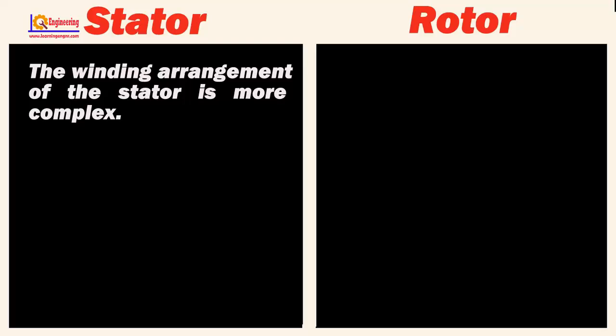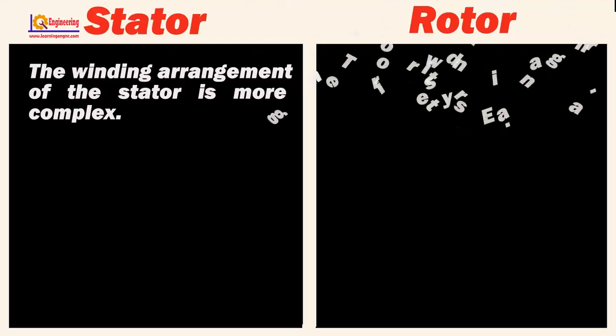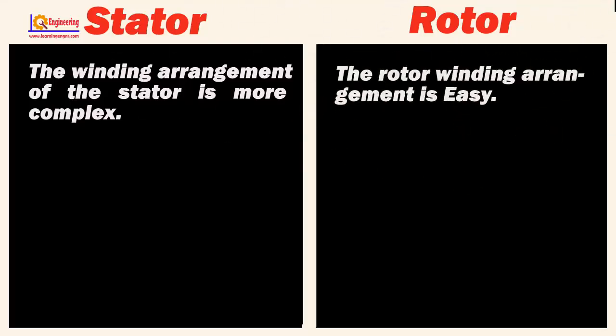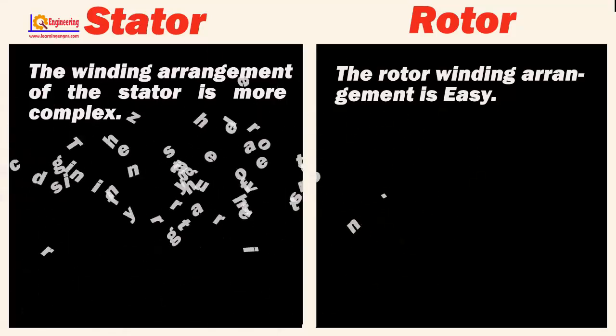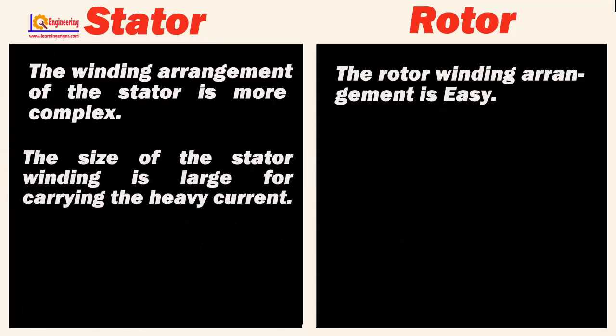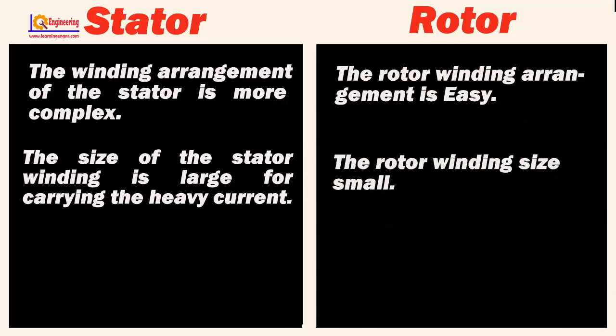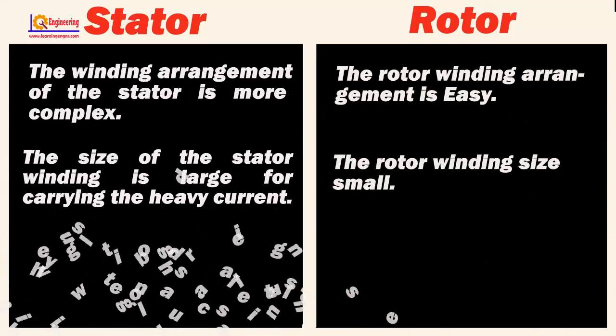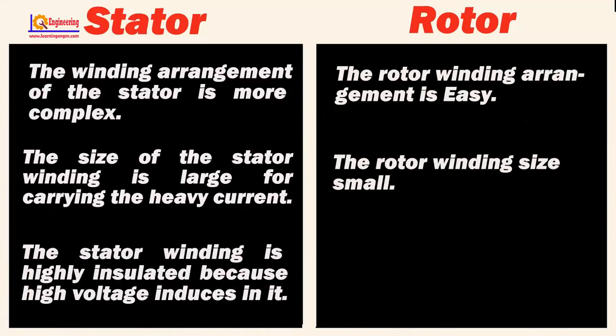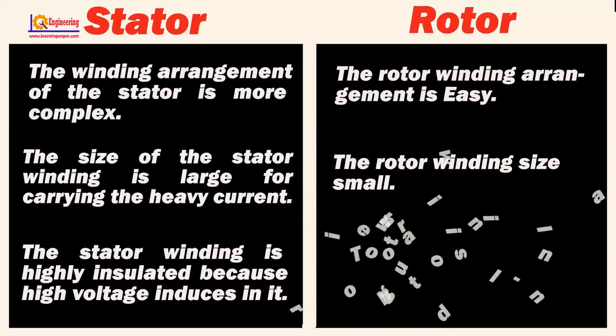The winding arrangement of the stator is more complex whereas the rotor winding arrangement is easy. The size of the stator winding is large for carrying heavy current whereas the rotor winding is small. The stator winding is highly insulated because high voltage is induced in it, whereas the rotor winding insulation is low.